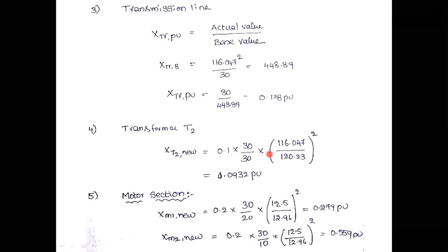So transformer T2 is 0.1, which he has already given, and 30 by 30, since MVA base new is equal to MVA base old, multiplied by kV base old divided by kV base new whole square. So next one is again the motor section. Similarly, you can also obtain the per unit impedances for motor 1 and motor 2.